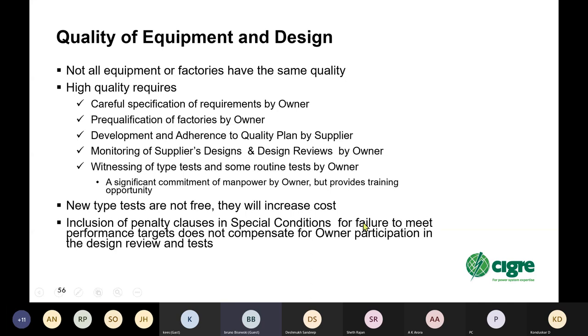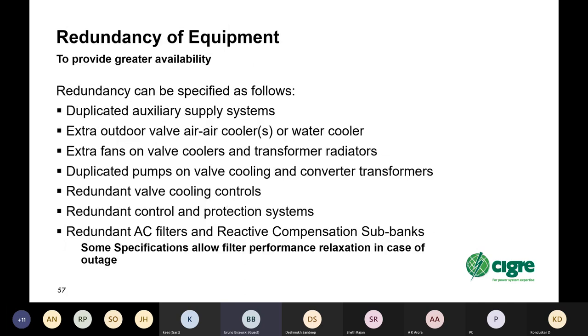And quality control, inclusion of penalty for not meeting reliability or failure rates doesn't compensate for the owner not participating in the design review and tests. It's really a good idea, if you do have a contract which allows you to participate in design review and approval, to really follow that up. And it's a good training opportunity, as well as ensuring that the quality goes into the installation.